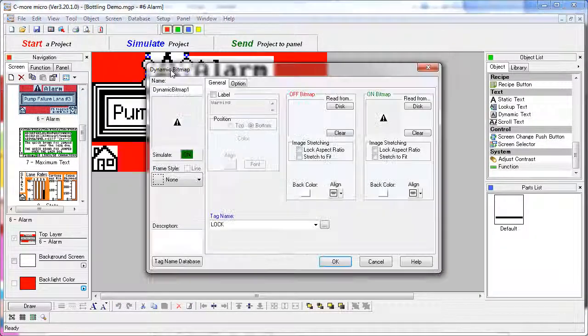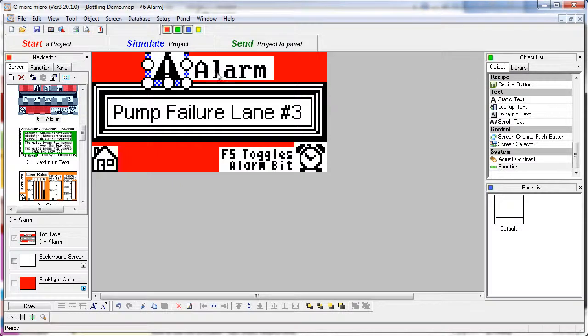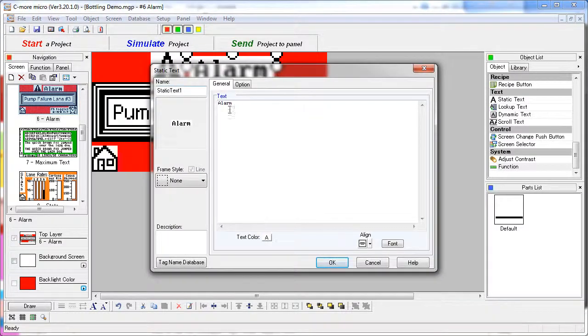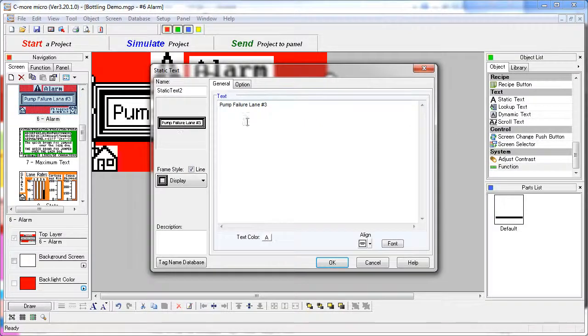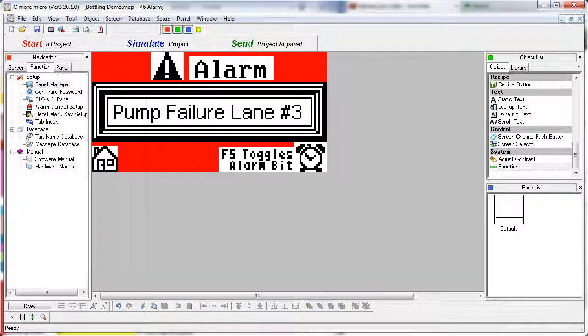This graphic is a dynamic bitmap that only appears when the LOCK tag is active. The way you do that is to only specify a bitmap for the ON state and leave the OFF state blank. These are all just static text blocks with the alarm — this big pump failure message and even this little note here. This is a static bitmap placed on top of a regular push button, which creates a graphic push button.